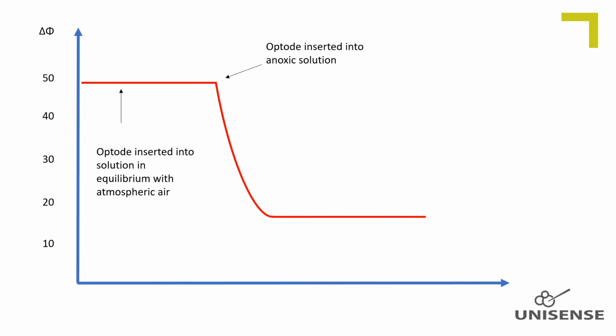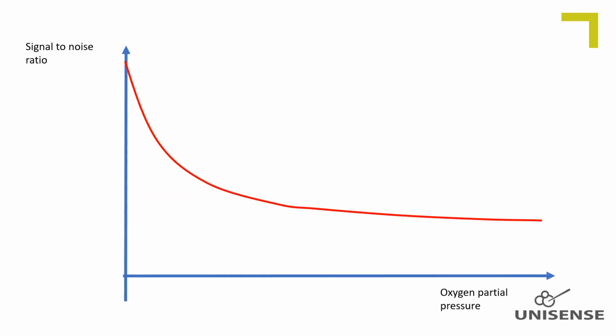For optodes which are used with the newest Unisense amplifier portfolio, these phase shifts for atmospheric and 0 partial pressure are determined and stored on the EEPROM, and thus they are factory calibrated. This factory calibration can be retrieved by the user, or alternatively the user can make his or her own calibration. As seen from the Stern-Volmer equation, neither the intensity nor the phase shift is a linear function of the oxygen concentration or partial pressure, and the linearity of the calibrated signal depends on calculations done within the optode meter/software.